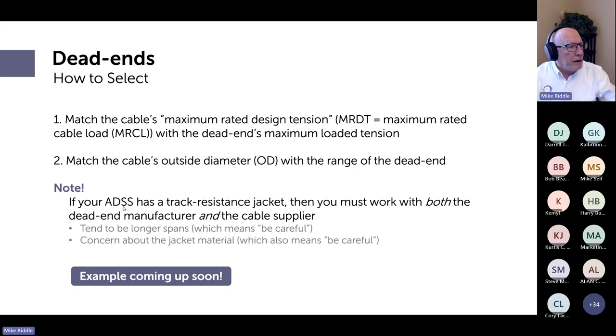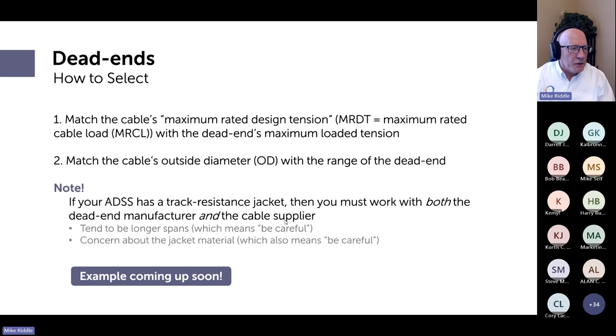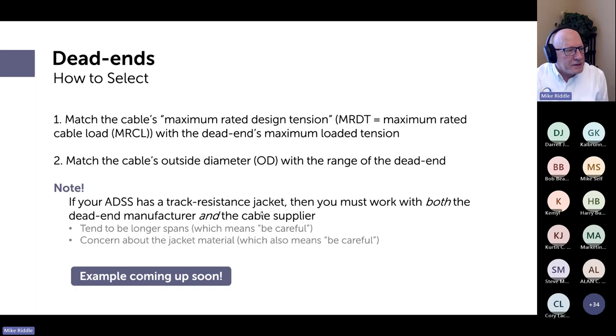Before moving on: if a cable has a tracking resistant jacket, you must work with both the dead end manufacturer and the cable supplier, otherwise you risk both problems and finger pointing. Tracking resistant jacket material is an issue in itself, and when you need a tracking resistant jacket your spans are typically longer, making the situation more challenging.